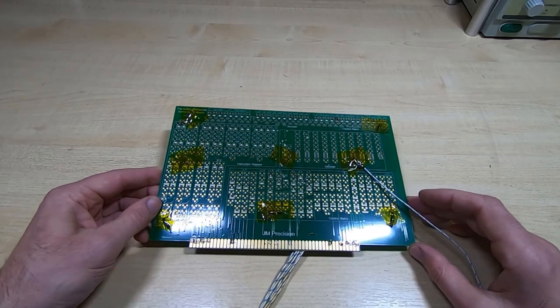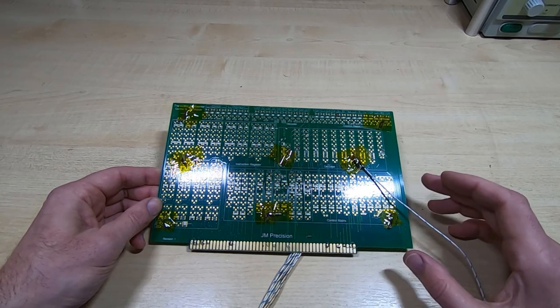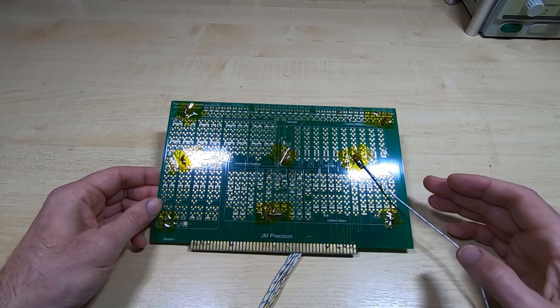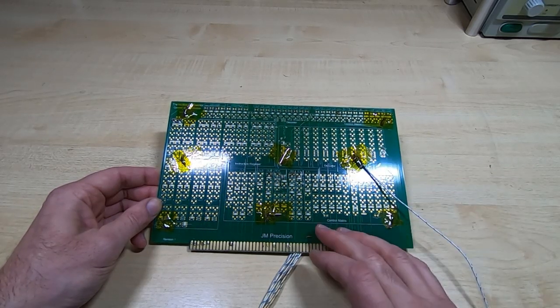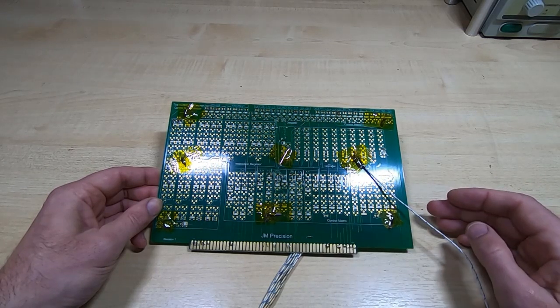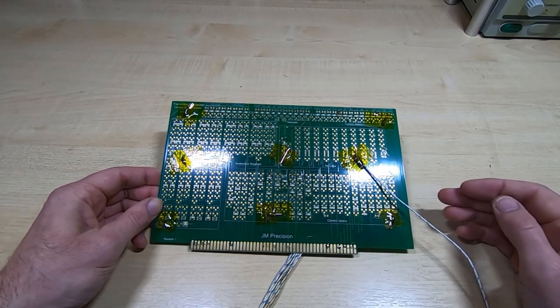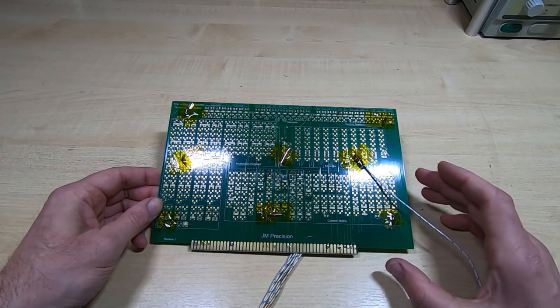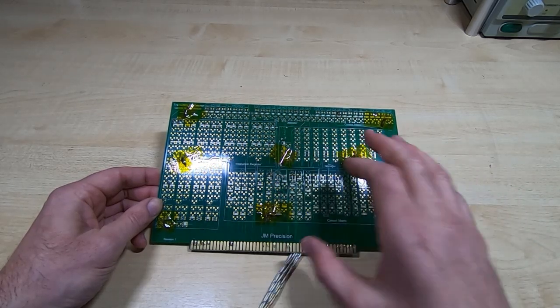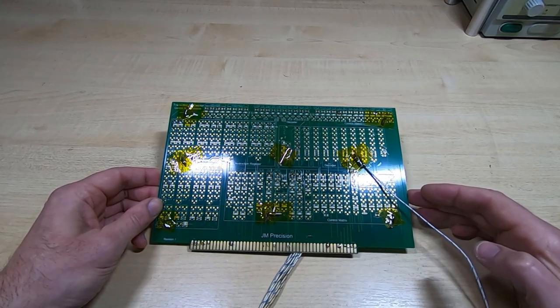As part of the ongoing process, what I do is every 50 runs in this case or thereabouts, I will take them off the board and recalibrate them. I calibrate them as a set to make sure they're all giving the same response, because it's the response that's important here. It's really the relative readings we're getting rather than the absolute accuracy that we're looking for.